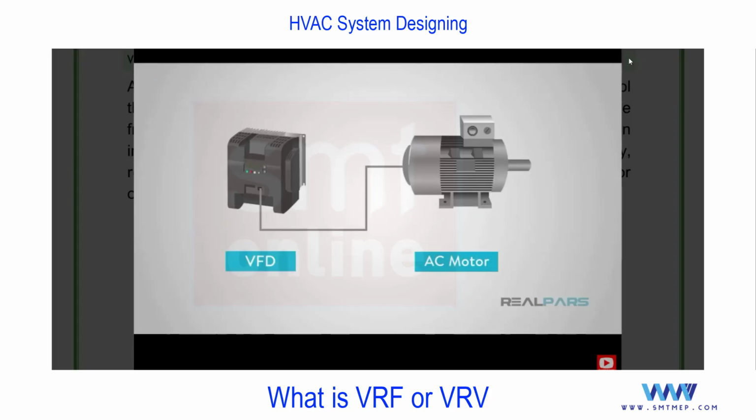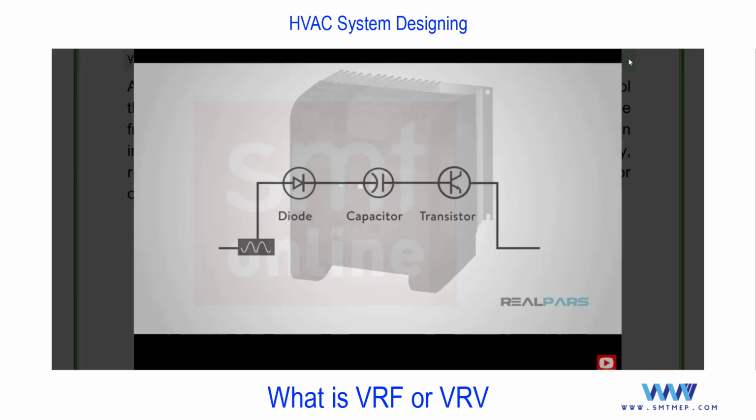Let's look back at what we now know. VFD stands for Variable Frequency Drive. They are used for controlling the speed of an AC motor. They are also used for ramping up a motor for a smooth startup, or to prevent a heavy load from straining the motor on startup. This is accomplished by adjusting the frequency delivered to the motor, with a setup of an AC to DC converter, then DC to AC converter.